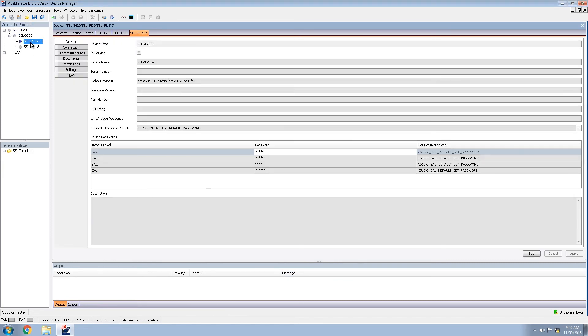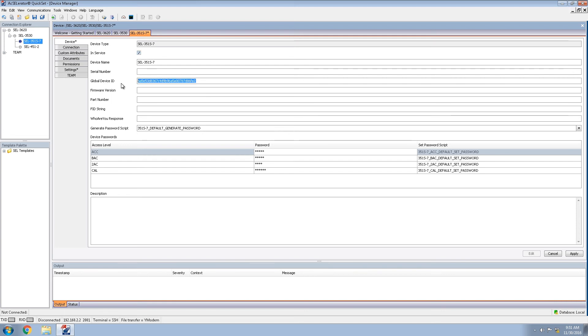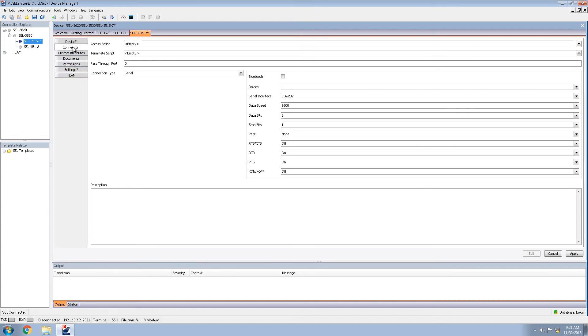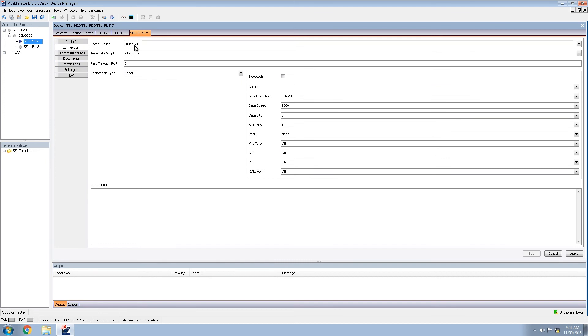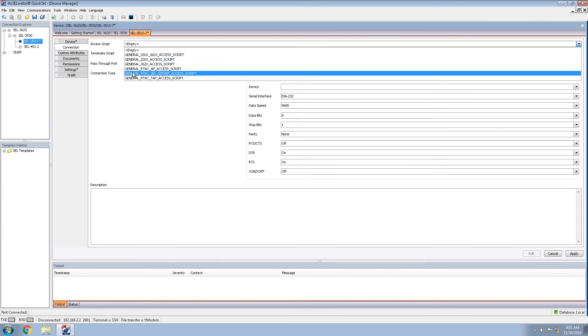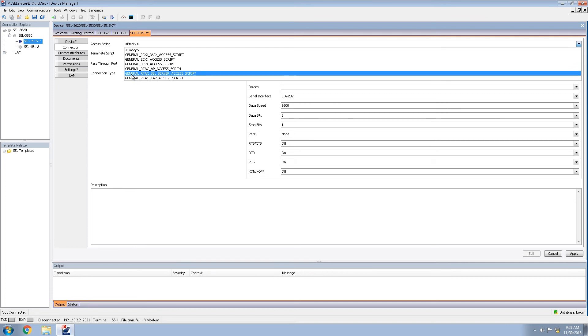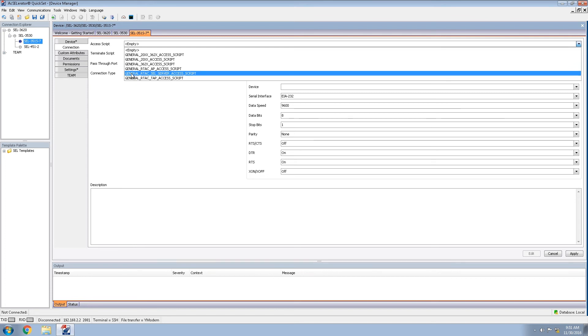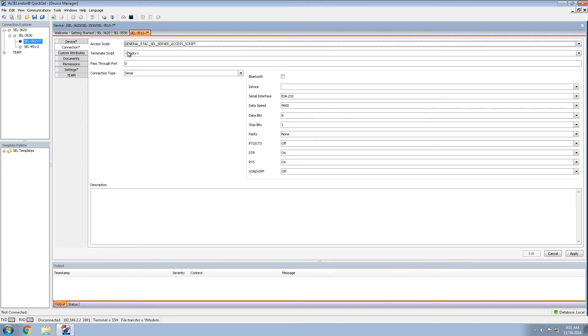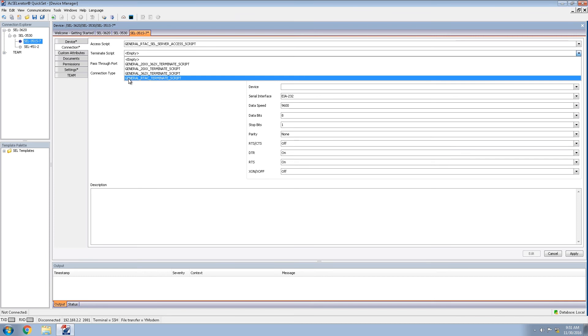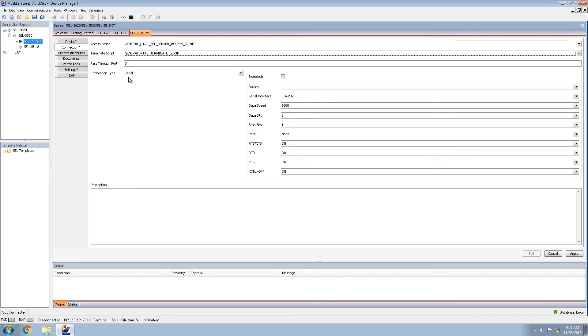We'll next move into the 351S, double clicking and editing. We will make sure that we have the in service checkbox, the global device ID, we will change to something meaningful, SEL underscore 351S. And moving to the connection type, we will be adding access scripts, including the general RTAC SEL server access script. And for the terminate script, we will be using the general RTAC terminate script.